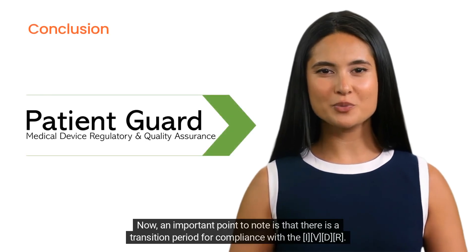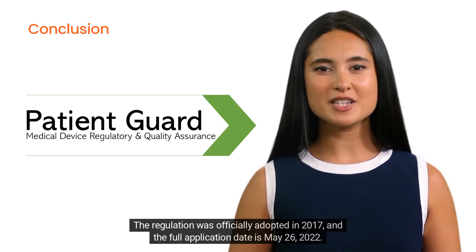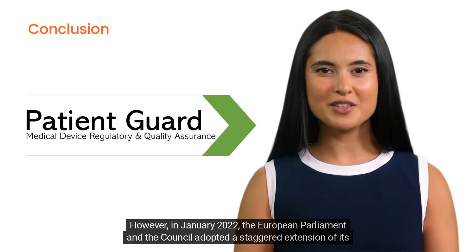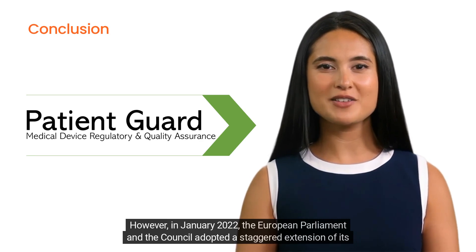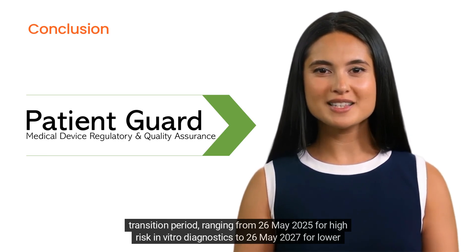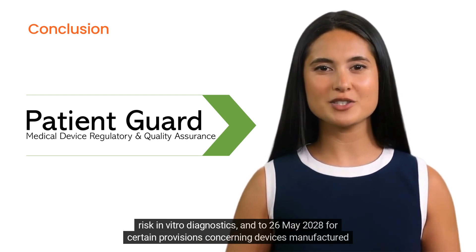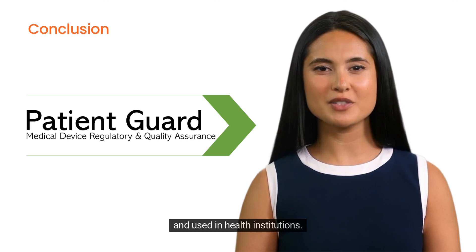An important point to note is that there is a transition period for compliance with the IVDR. The regulation was officially adopted in 2017, and the full application date is May 26, 2022. However, in January 2022, the European Parliament and the Council adopted a staggered extension of the transition period, ranging from 26 May 2025 for high-risk in vitro diagnostics, to 26 May 2027 for low-risk in vitro diagnostics, and to 26 May 2028 for certain provisions concerning devices manufactured and used in health institutions.